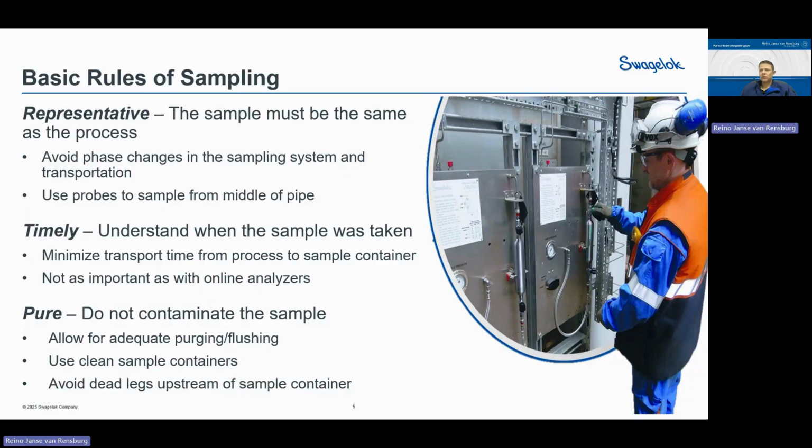Okay, so we need to minimize transport time from the process to the sample container. It's not as important as with online analyzers. With online analyzers, you generally want your response time to be within 1 minute. With grab sampling systems, that's a little bit more.